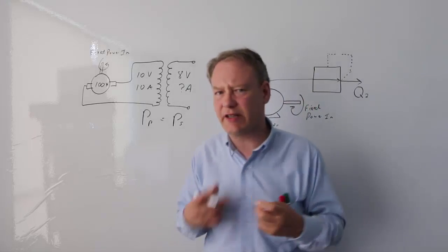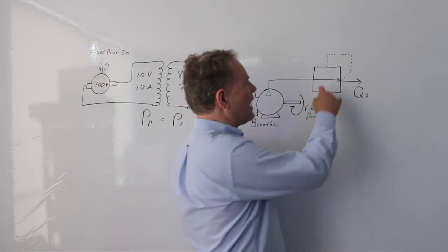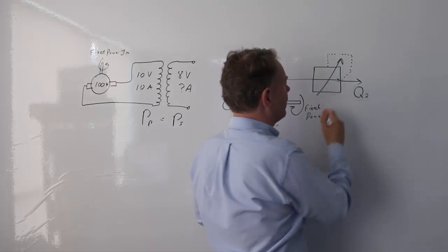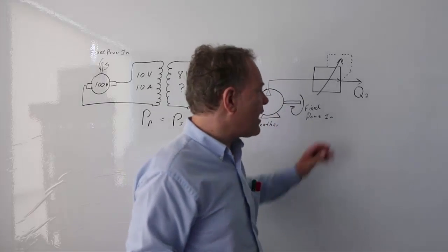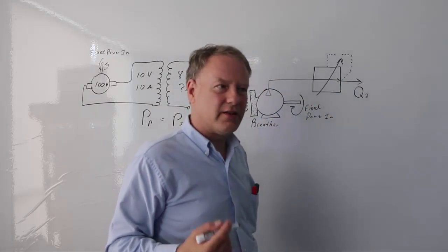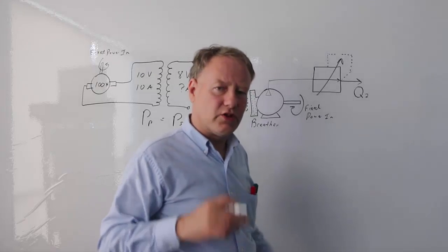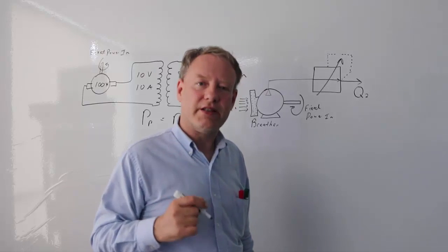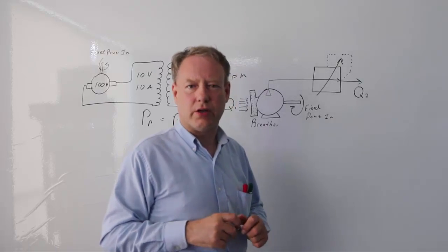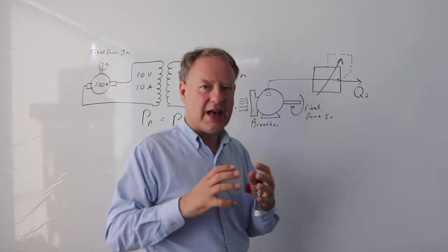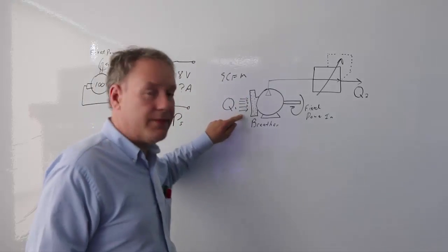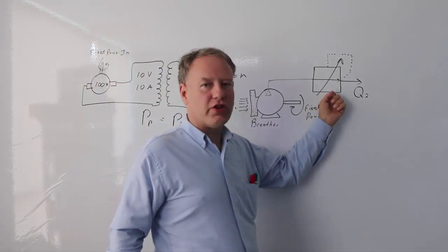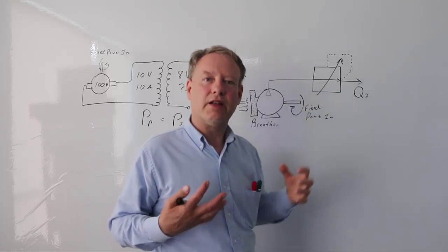The outlet flow rate is actually dependent on pressure. If this pressure regulator is adjustable, the flow rate and pressure out here are linked together because of the gas laws. If I increase the pressure, I'm compressing gas, so the volume of the same amount of gas coming in has changed — it's gone down. So as I increase the pressure, my available flow rate goes down.